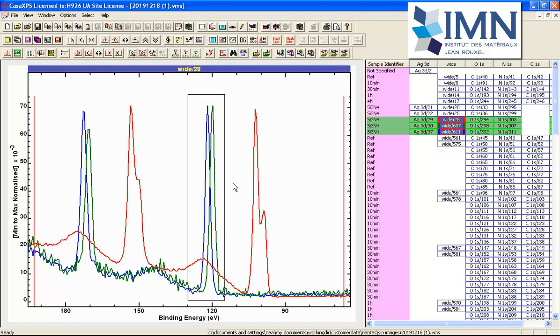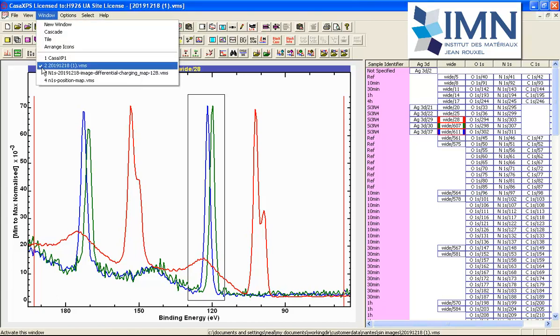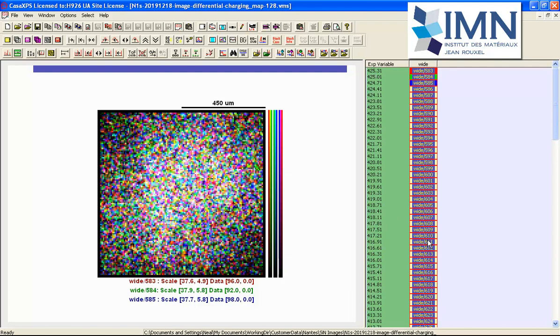If it's the analysis area, then we are suggesting that we've got differential charging. That is to say the charge compensation is not producing a uniform charge state across the sample. To work out if we've got differential charging, we can measure a set of images. In this case the images are all acquired with energies that correspond to the nitrogen 1s peak.